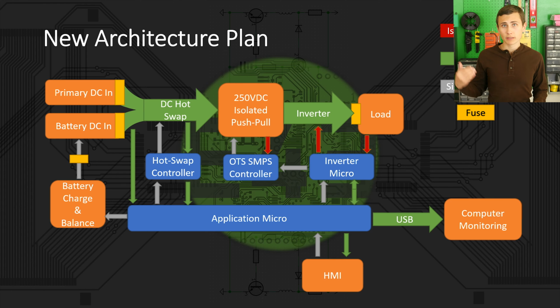However, this ramping of the common mode voltage slowly will allow for fault conditions to trip when smaller voltages and currents are at play if something does go catastrophically wrong. This will help to prevent damage to connected equipment. Temperature monitoring of the various supplies has also been added, which prevents overpower conditions from causing thermal runaway if something like a cooling fan were to break. The design now has over temperature, over current, and over voltage monitoring capability. That is huge. If any of these limits are exceeded, the low-level micro has the ability to shut everything down.